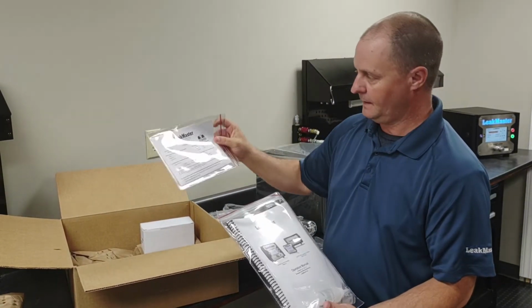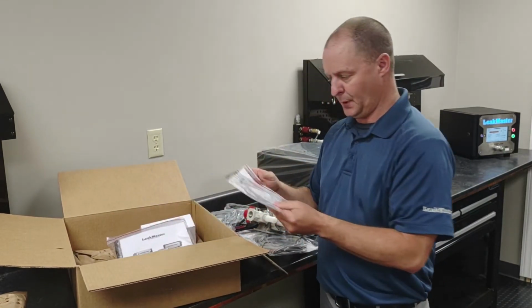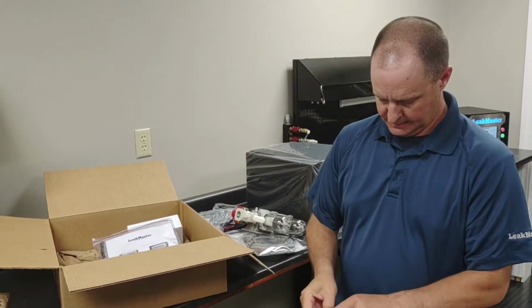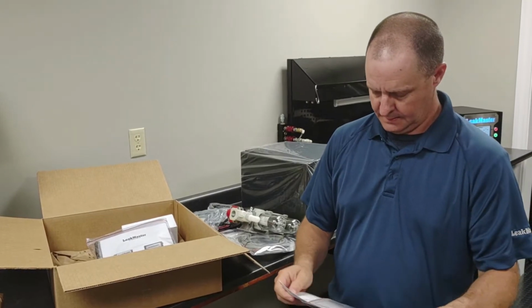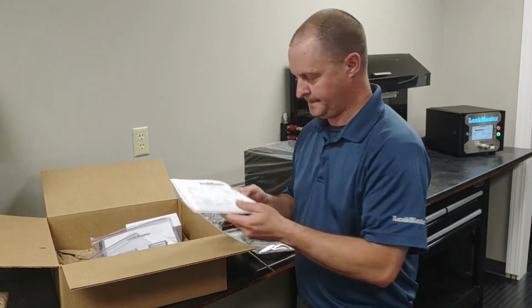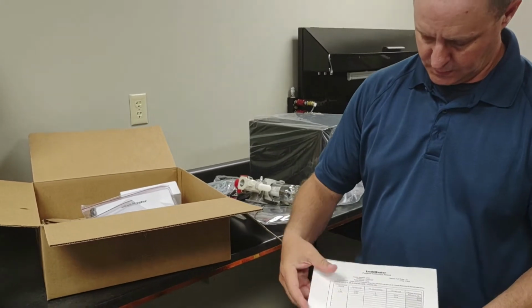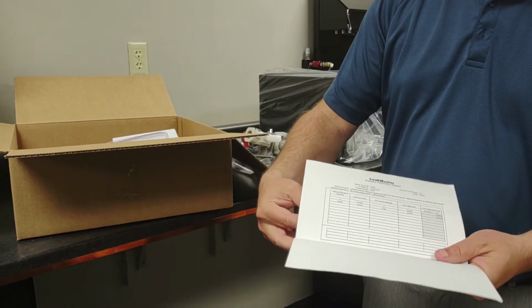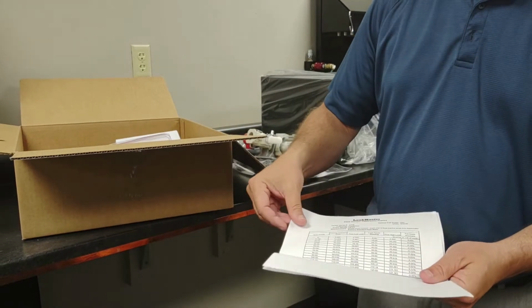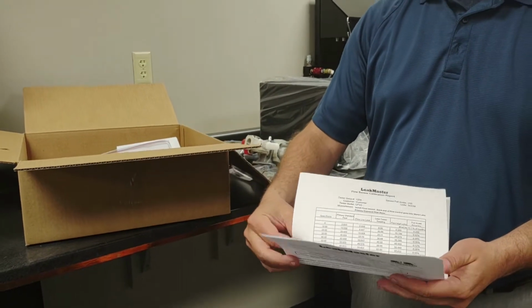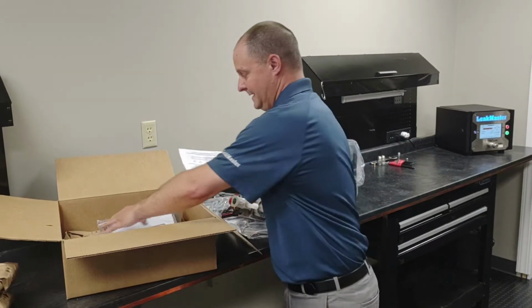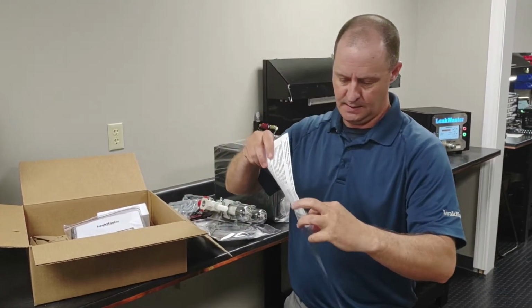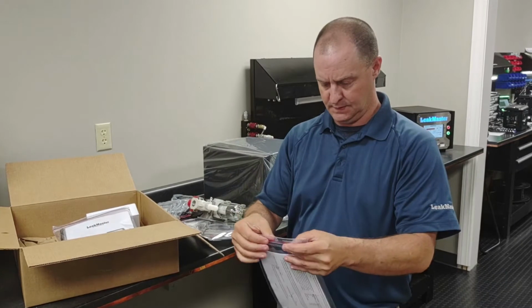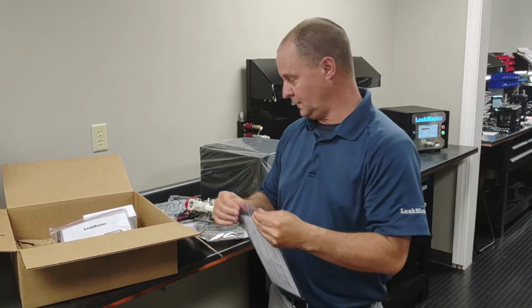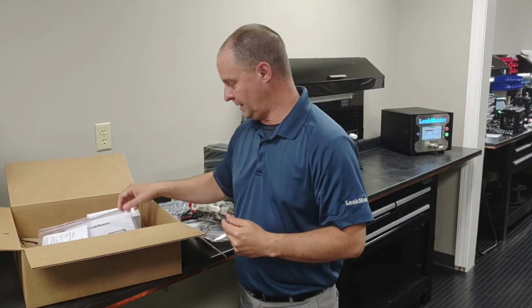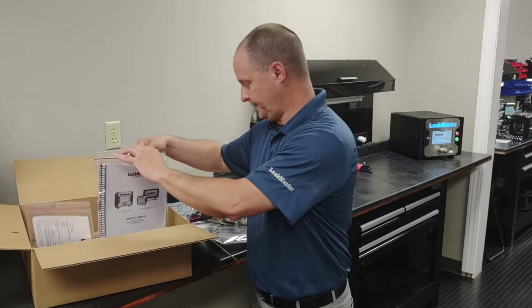And we've got cal certificates here. If you purchased a calibrated leak orifice, it's going to come with an accredited calibration certificate. On an UltraFlow, you're also going to have your pressure calibration report and your flow calibration report for your flow sensor. Now this is all important. It's important to keep all of this information and pass it on to the end user so they can properly store this in their gauge lab for calibration and recertification purposes.